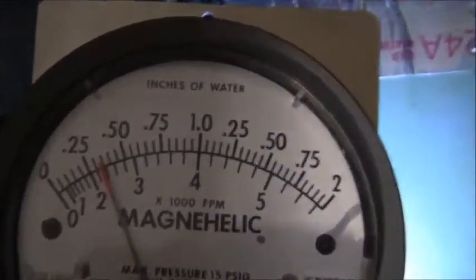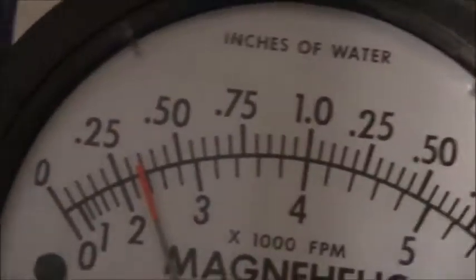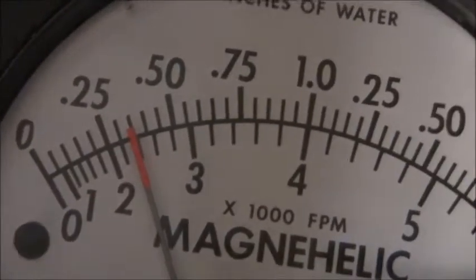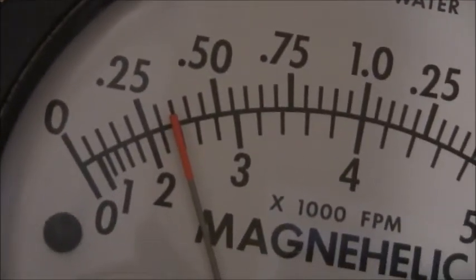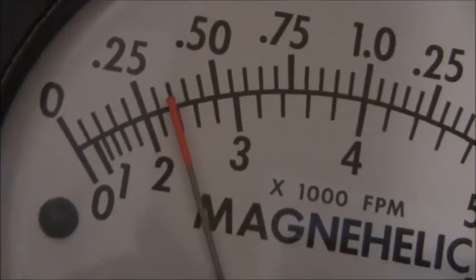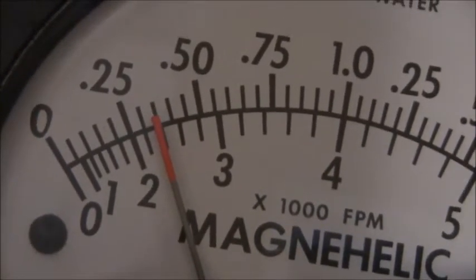So that is what I'm going to use for my reading right now. So let's get the magnehelic gauge up here, make sure it's nice and flat, and use the high side reading. The low side reading is just going to atmosphere, so I'm not going to plug that into anything, and I'm just going to plug in this high side reading right there, and you can see it come up on the magnehelic gauge. Now let's write that number down. That number is 0.35 between these 2 points.